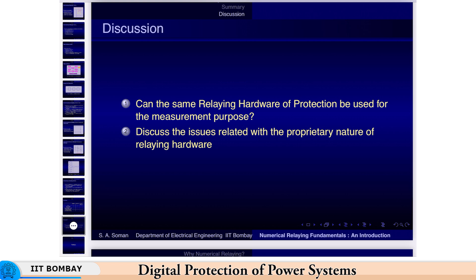Okay, so that's why the same hardware... this can happen with CTs also, because for protection CTs, we saw that 20 times and all that. If you have current transformers which are accurate to 20 times, getting those same current transformers to be accurate for very small currents, 1% or 2% like that, is difficult, because the magnetizing current of the CT itself will be very high. So these kinds of compromises will be there.